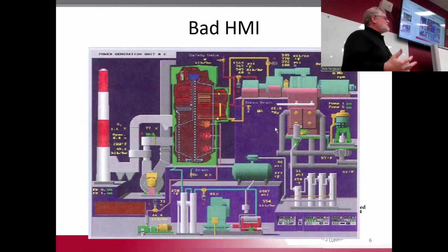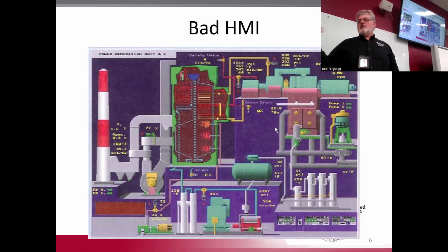So HMI design back in this day was selling because of pretty pictures, but operators were paying the price. Operators hated these screens. The first time they looked at it, they're like, that's cool. The first time they ran it for a while, they're like, all right, how do I go look at this data? All right, you page down over here. So you had many, many long, painful discussions with operators over screens like this.